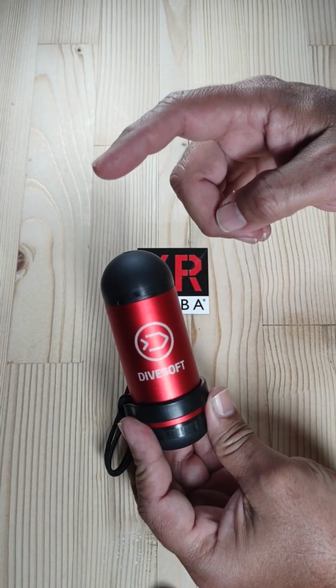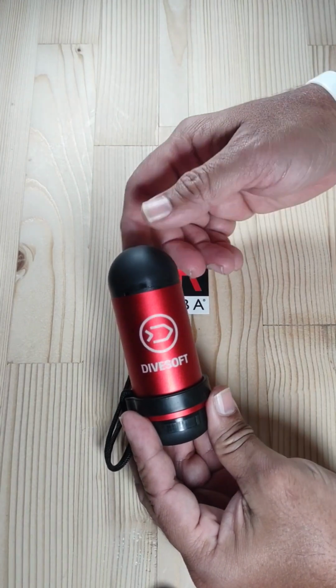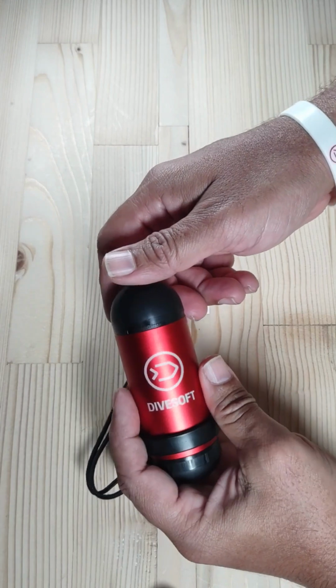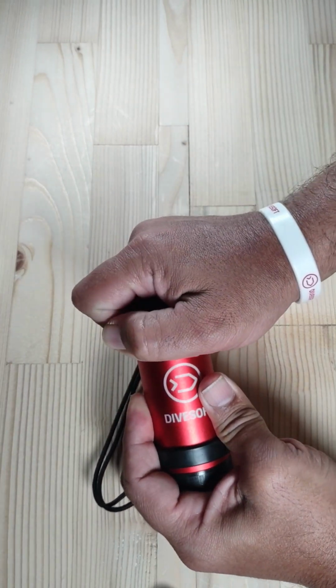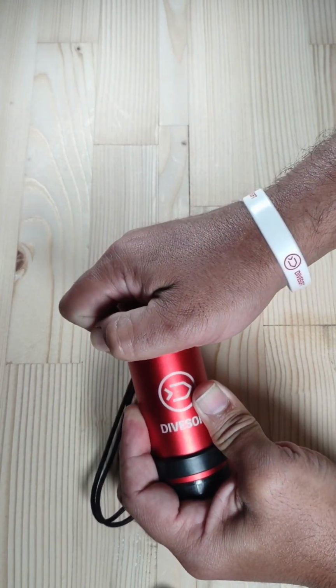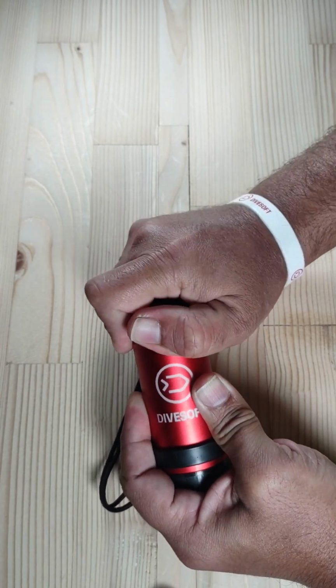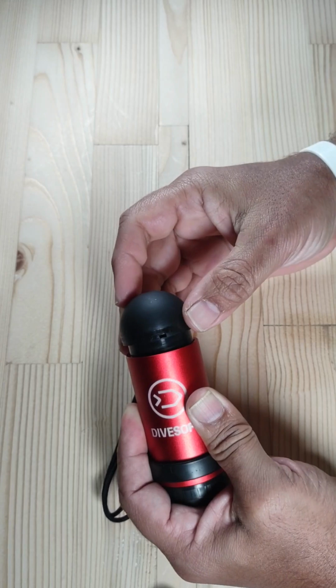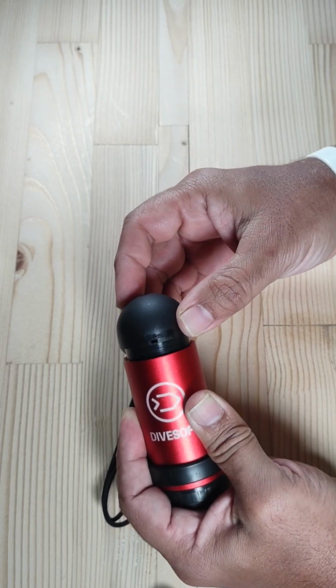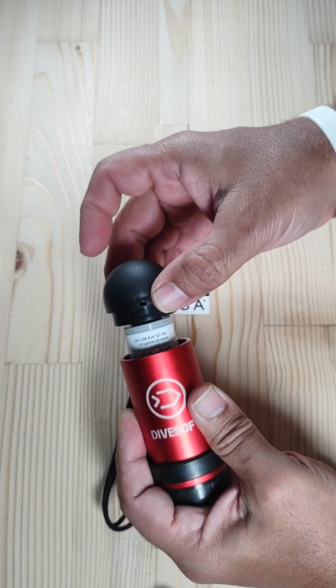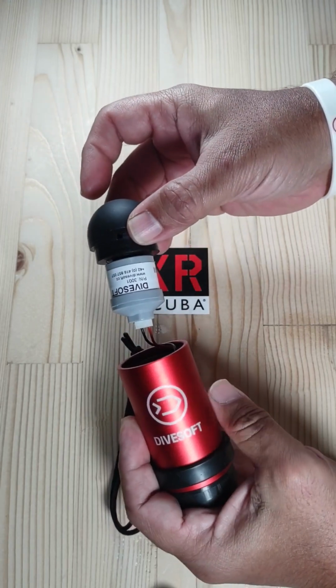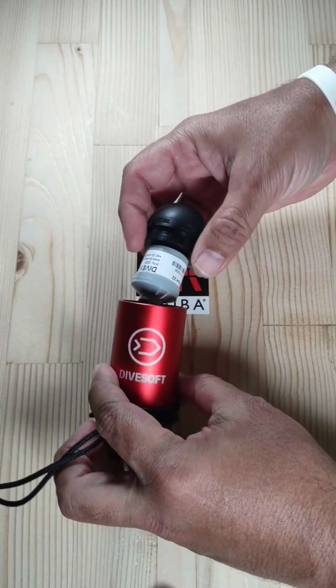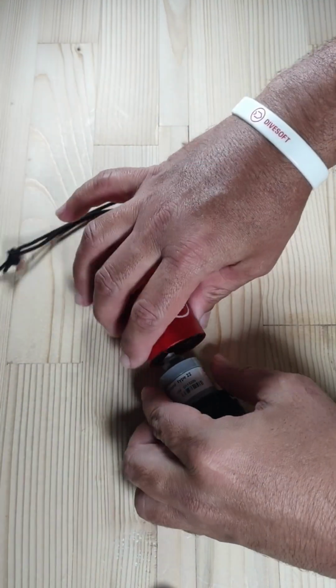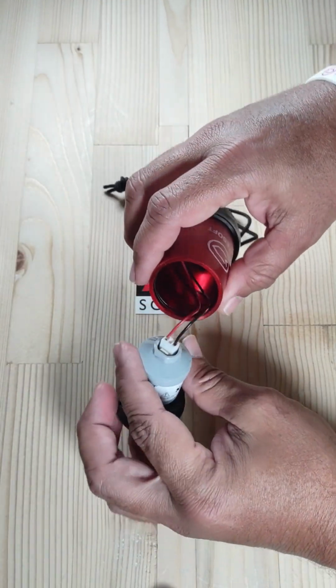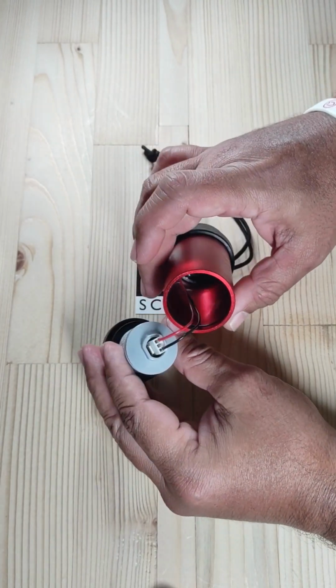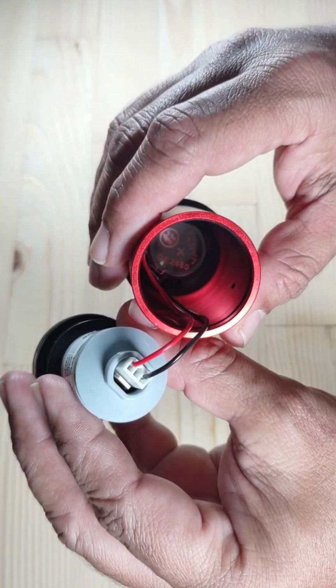If you need to replace the oxygen sensor, you go to the top and do the same thing with the head. You just twist it and just pry it open. It's not a screw, it's a push fit. You pull it out until you can see the sensor. You have to be careful here that you don't pull these wires. There is enough wire to play with, but don't pull it out too much.